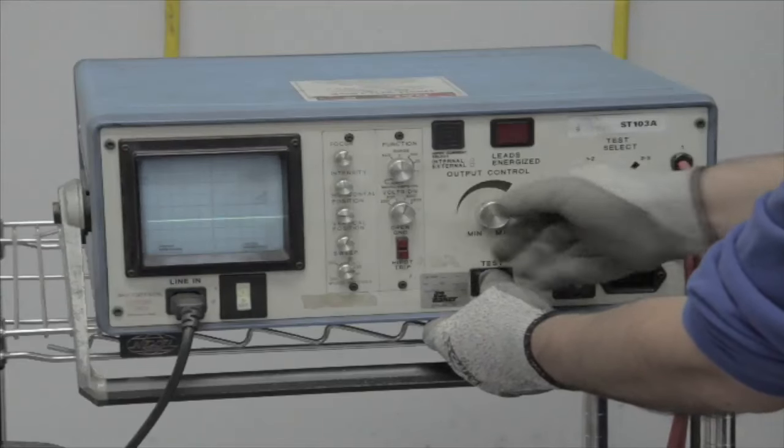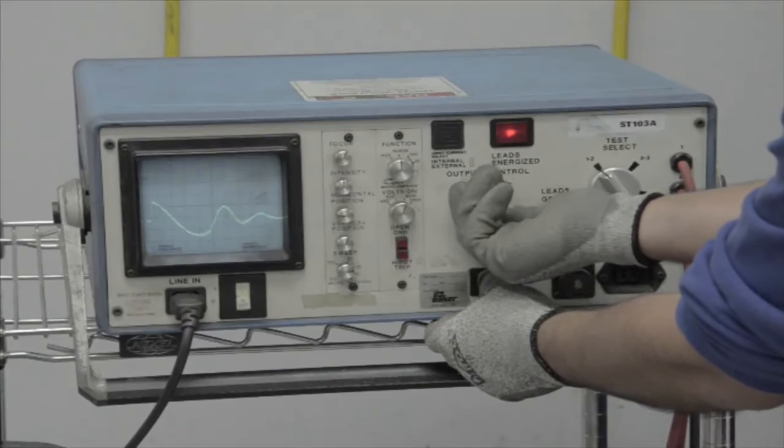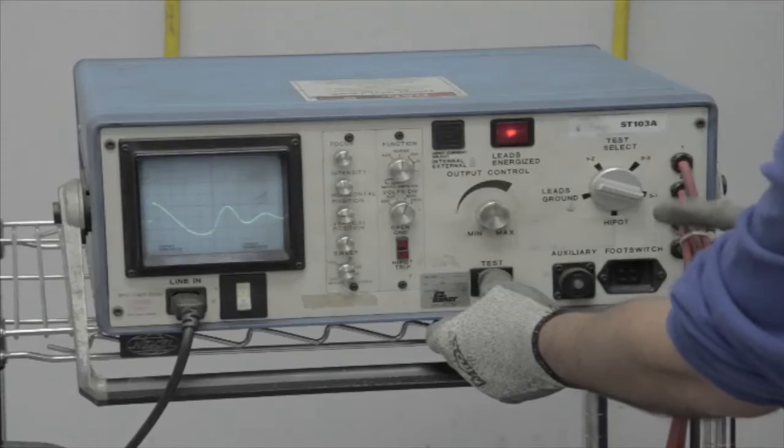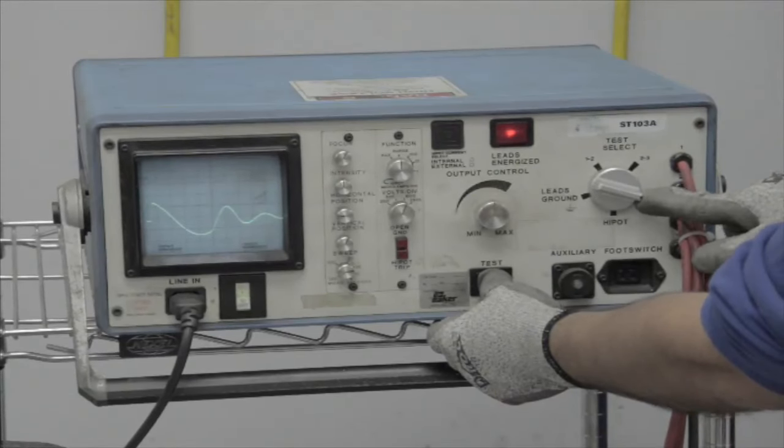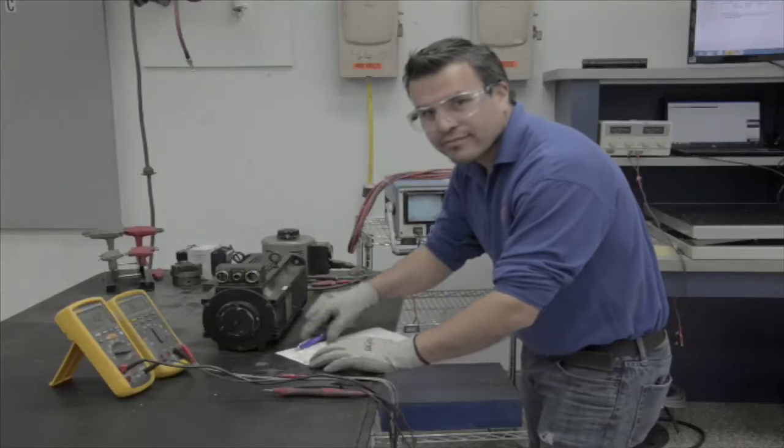As you can see on the screen of the surge tester, as the high voltage is applied, the readout from phase one to phase two is perfect, phase two to phase three is perfect, and phase three to phase one is also perfect. This motor does not need a rewind, however, if it did, we do have the capabilities right here in this facility to do a full rewind, even on servo motors.